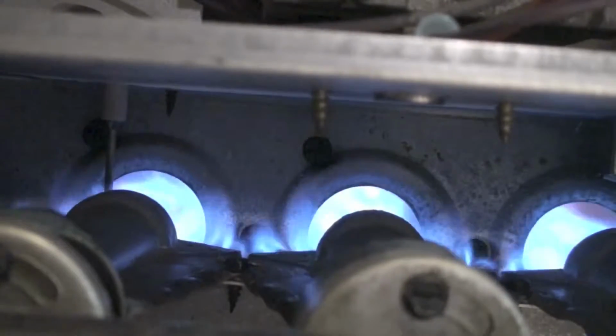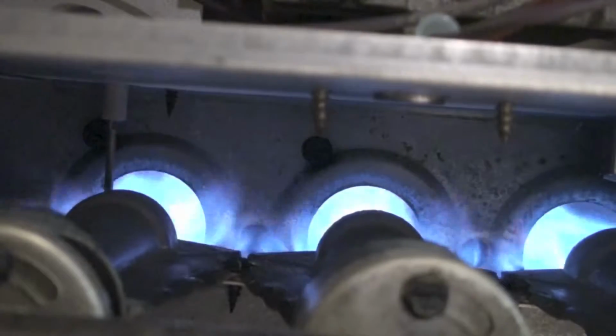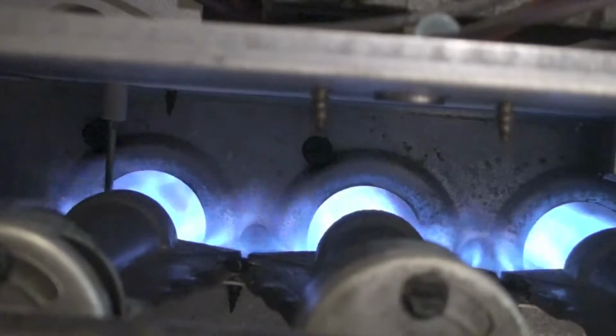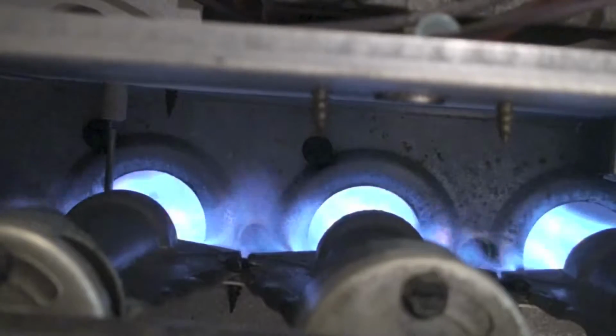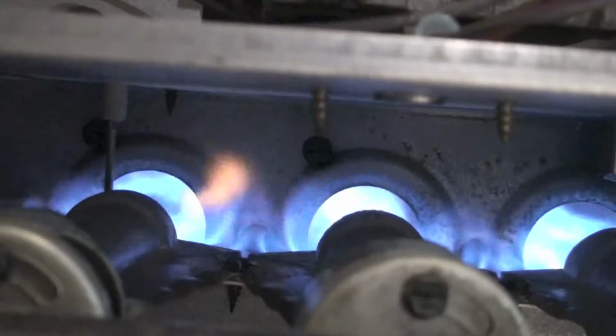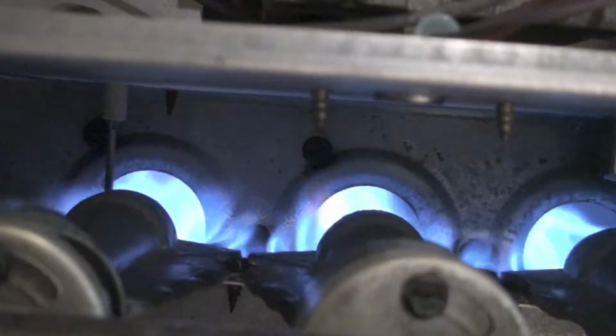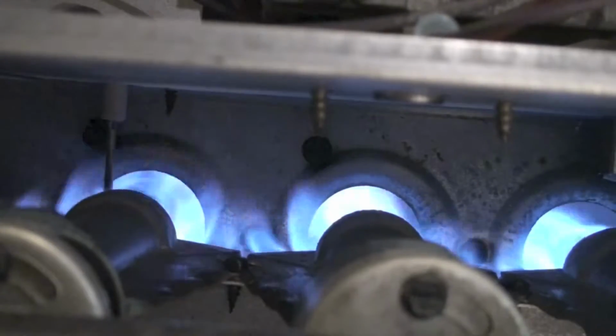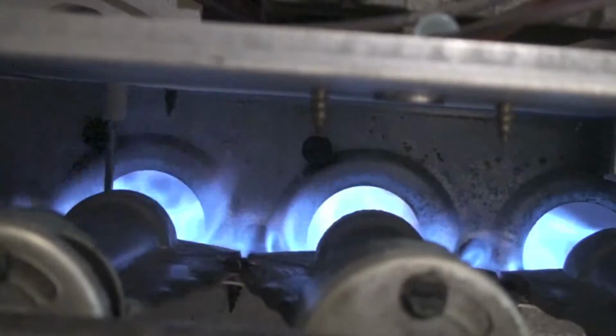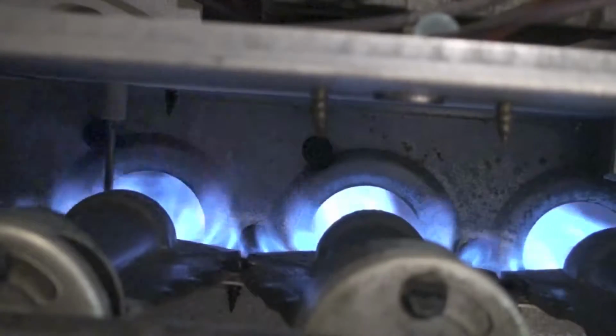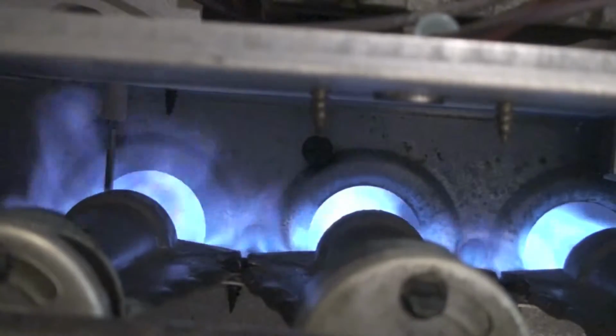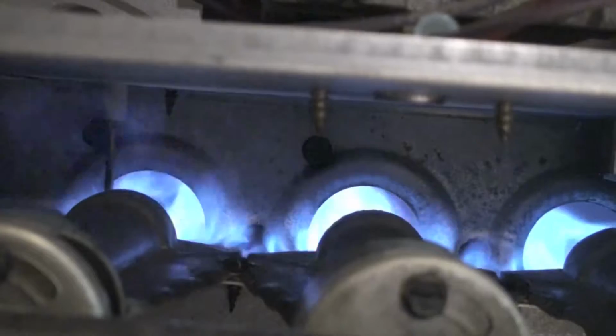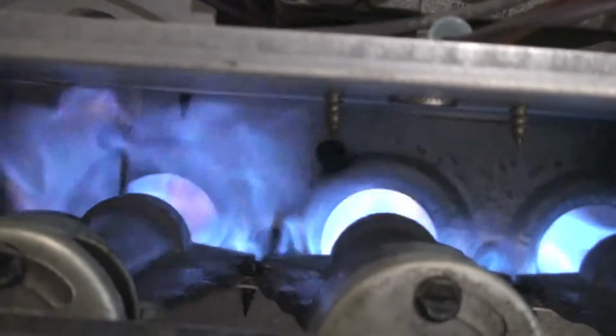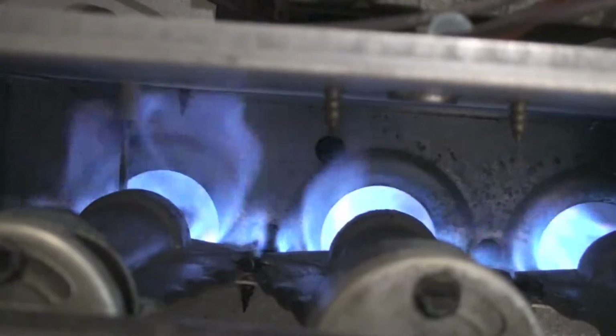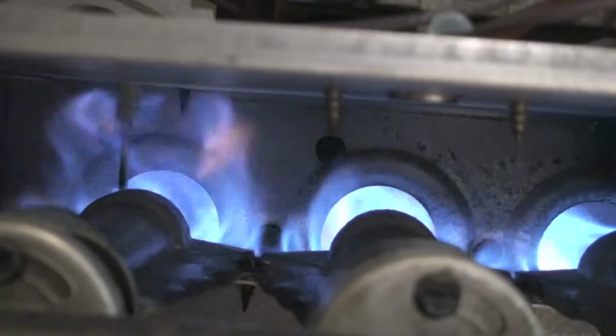Okay, blower has come on. Now you look at especially that left burner. See that flame that's starting to lick upwards? And you can see it's all really ruffled inside there. When the blower started, it started blowing air back in. And now it's really flopping up there. It actually started blowing air from the blower assembly into the burner compartment. Now it's doing it on both the 2 left burners.